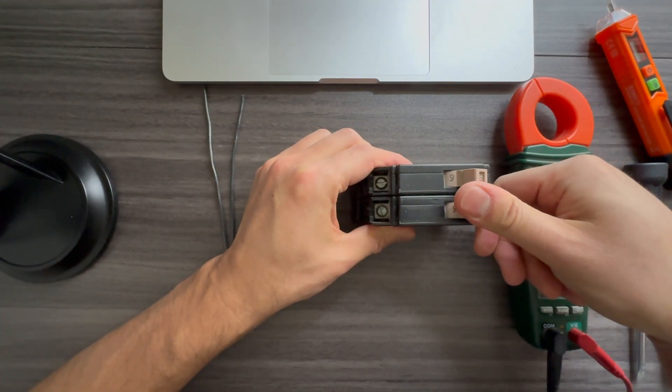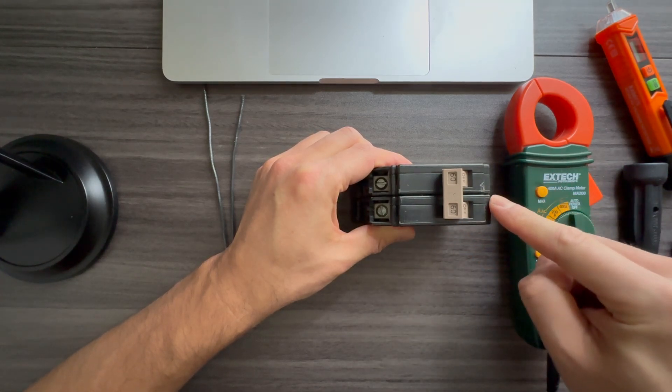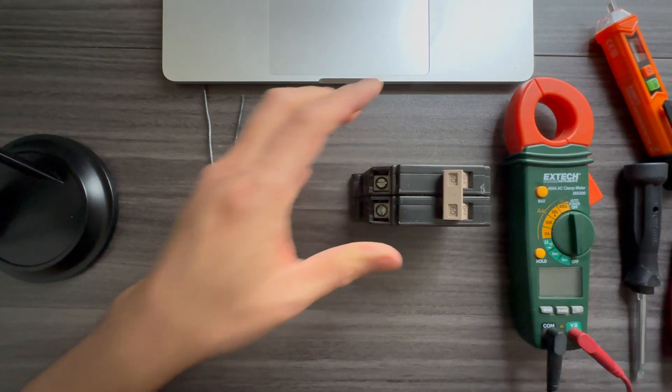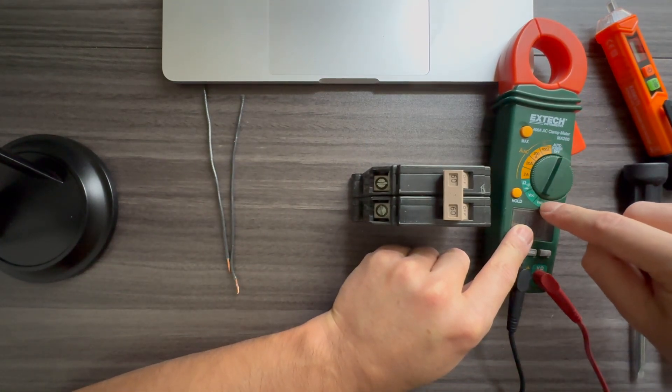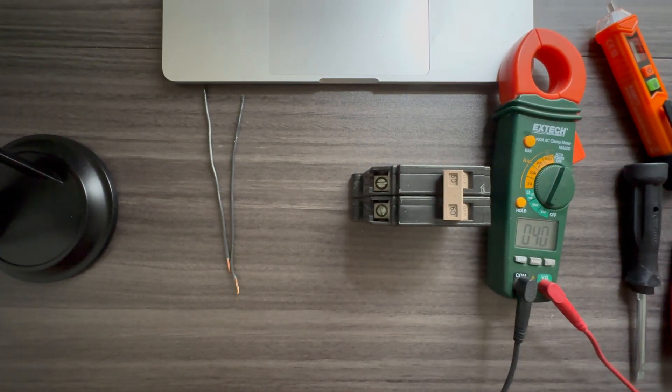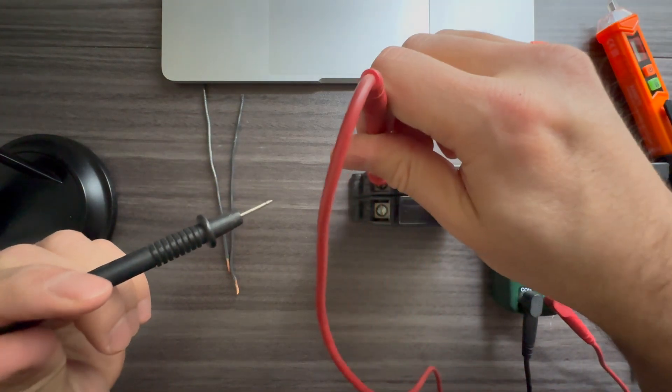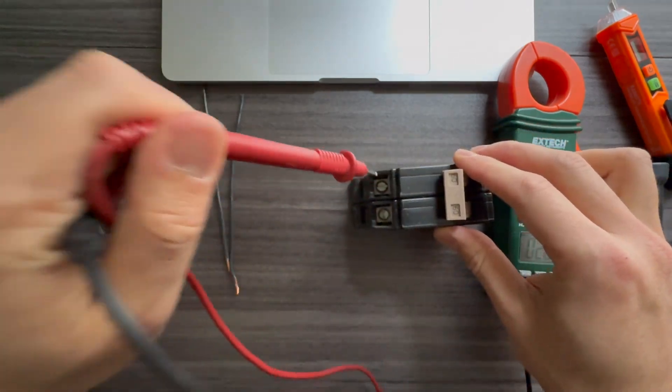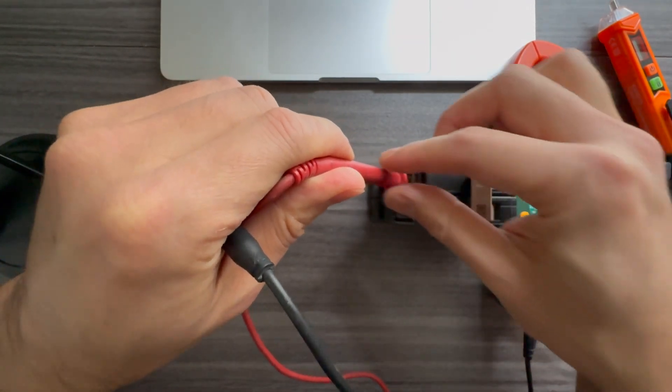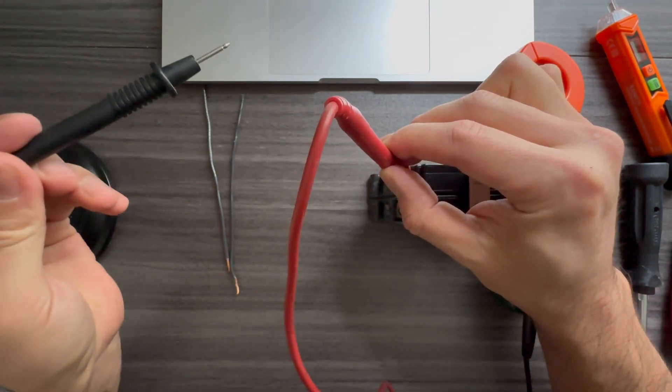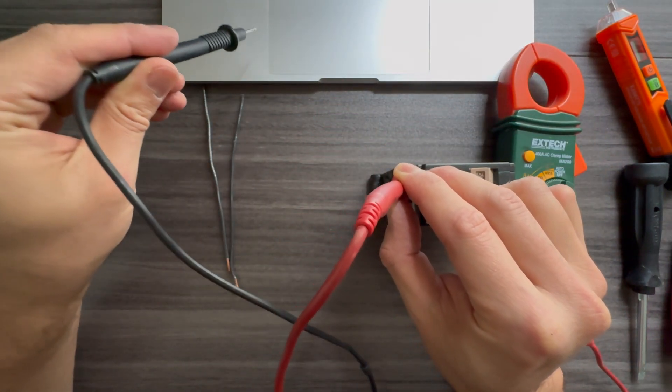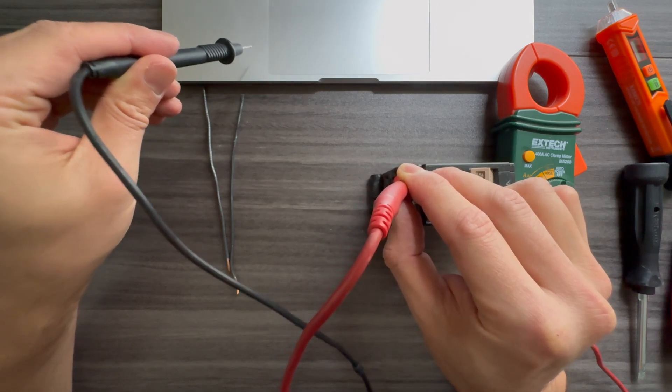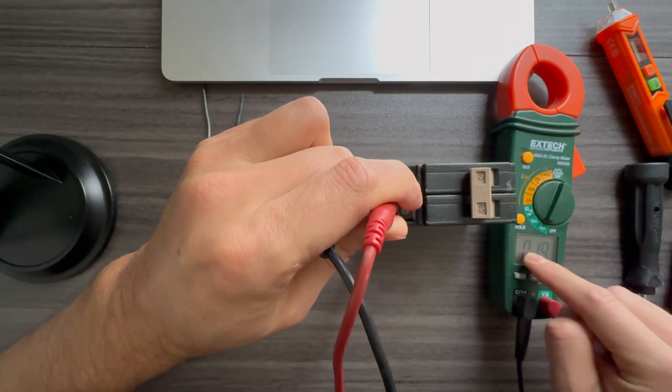Remove this as well, set it on the side, put a wire nut on that wire, and we try to turn it on. If we try to turn it on and it stays on, next step would be to put it on volt AC. And then what we're going to do, if it's a single pole, one terminal, we're going to touch this screw that we removed the wire from. We're going to touch this terminal and then with another terminal of the voltmeter, we're going to touch the panel, let's say ground or neutral, whatever.